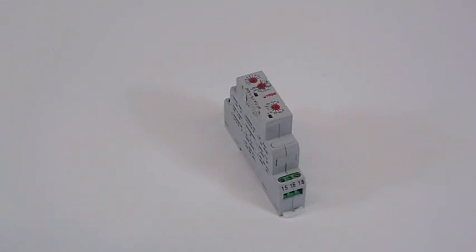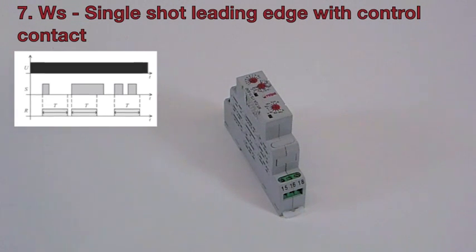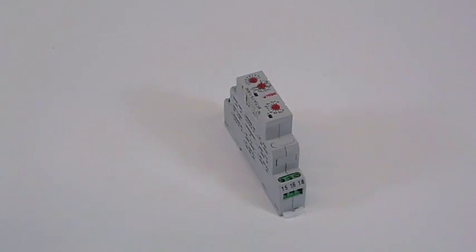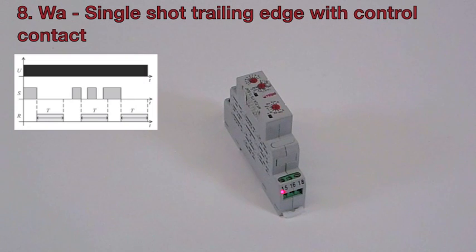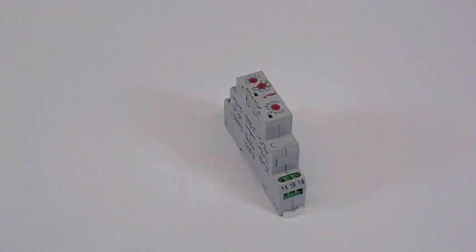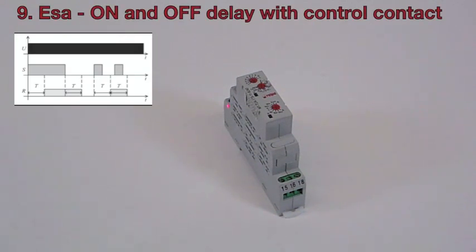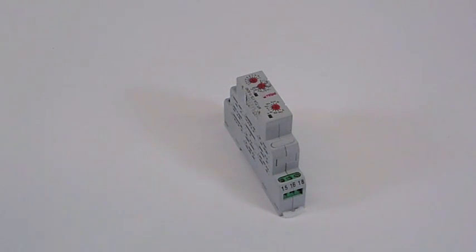The timer controls a single pole, volt free, changeover relay, rated at 16A. The output on pins 15, 16 and 18 at the bottom. The input for the supply is A1, S and A2 at the top.